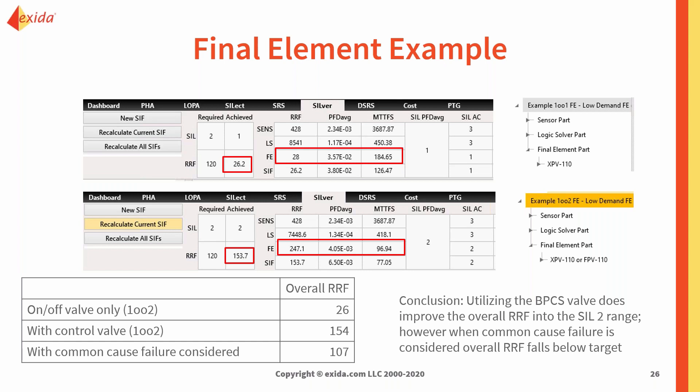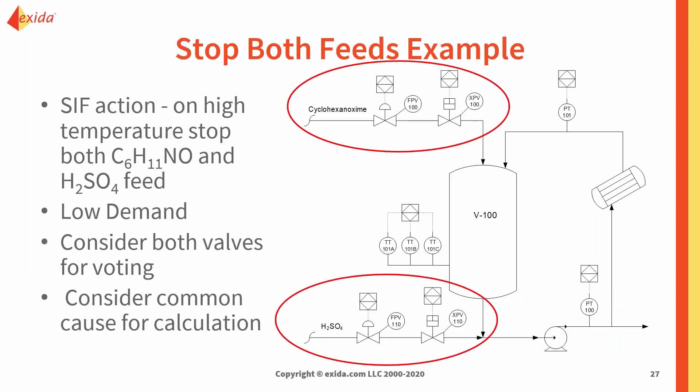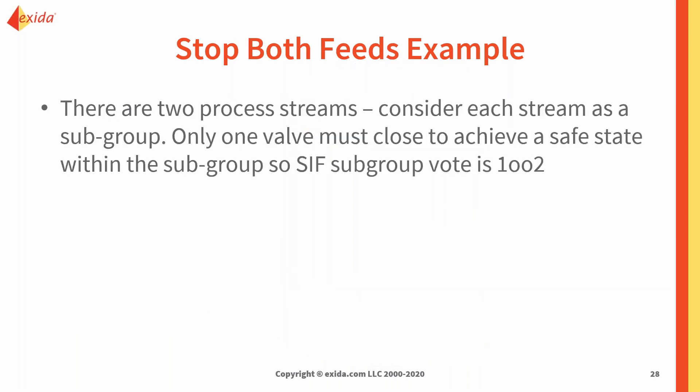Without common cause adjustment, utilizing the BPCS valve could theoretically take us into the SIL 2 range. But when we recognize the common cause failure, it falls below target. If we can't add full redundancy on our safety function, we may have to look at other provisions to get this compliant with that architecture. So we're stepping back, and the engineers have decided we need to stop both feed streams to achieve a safe state.